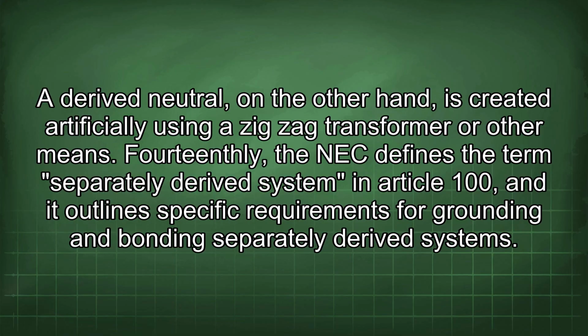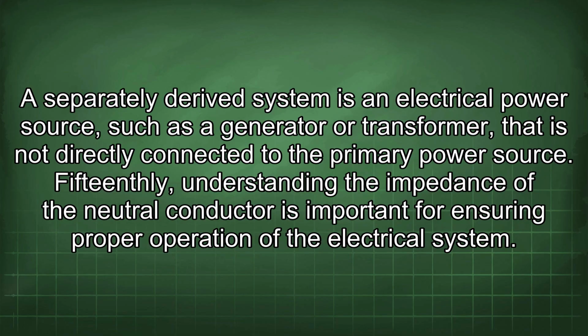14thly, the NEC defines the term separately derived system in Article 100, and it outlines specific requirements for grounding and bonding separately derived systems. A separately derived system is an electrical power source, such as a generator or transformer, that is not directly connected to the primary power source.